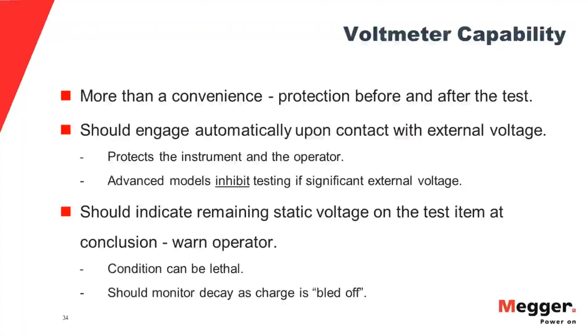The old units, if you ever run into some of those old Meg types, for instance, you will actually see sometimes they had a discharge switch on the panel where the operator would then engage a discharge circuit to bleed off the stored charge at the end of a test. Well, suppose he forgets to do that. So we'll talk a little bit about that, because it's extremely important in terms of safety. And if you're ever dealing with new hires, apprentice electricians on their first day on a job or something like that, always make sure that they know about the discharge function on an insulation tester.